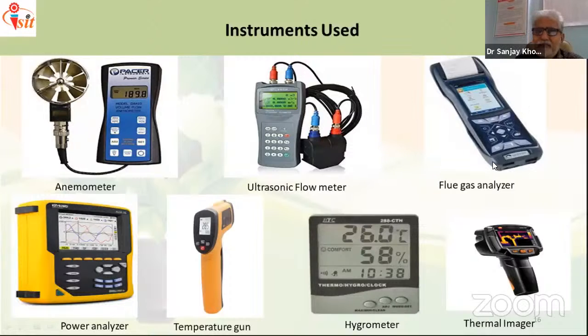Now another one is the flue gas analyzer. This flue gas analyzer is used to measure the combustion of the fuel burnt inside the furnace or the boiler. There is one probe, and you just have to put that probe in the chimney of the boiler or furnace. The setting has to be done on the basis of which type of fuel is being used. Directly with the help of the flue gas analyzer, we get all the compositions inside the flue gas. It may be SOx, NOx, carbon, oxygen O2, carbon dioxide, carbon monoxide. So many data points we get from this flue gas analyzer. With this data, we can estimate boiler efficiency by the indirect method. This is a very good instrument, essential for all thermal applications. Another advantage is that it can be connected directly to the computer, so the data can be taken into Excel and analyzed.